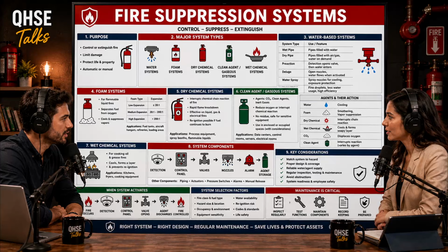Exactly. If a CO2 system discharges while workers are inside, the oxygen level plummets instantly. It poses a lethal, toxic, and suffocation hazard. People will pass out in seconds. That's terrifying. And furthermore, the physical discharge is incredibly violent. It creates a deafening roar that can exceed 100 decibels, and the rapid cooling creates a dense white fog of dry ice snow that drops visibility to zero. It causes massive panic. So if the system is that dangerous, how do safety engineers mitigate that risk?